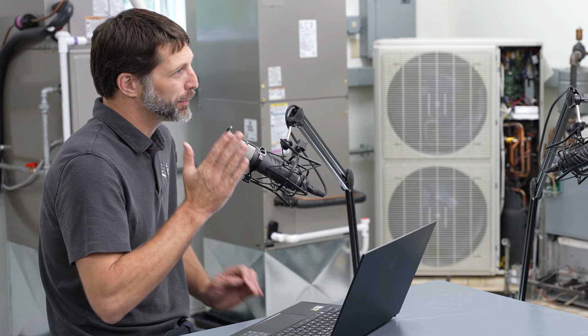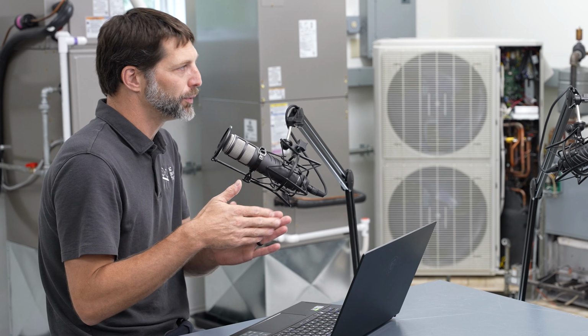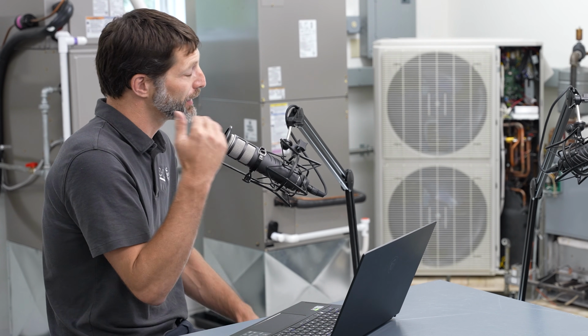Yeah. So there's also the whole flux situation. When you're dealing with solder, you have to put a flux in, and that flux could be a creation of acid inside the system because it's not going to be exiting the system. So that's an issue. And the nice thing about silver soldering is you don't have to flow nitrogen through while soldering because you're not at a high enough temperature to really need it. But the reality is it's not that hard to just go ahead and flow nitrogen through at 3 to 5 cubic feet per hour while brazing. And the reason we do it while brazing is so that we don't have oxidation occurring inside the tubing, and so we don't have that maybe gumming effect or clogging of the strainers or filter dryers or a lack of lubrication at the compressor.